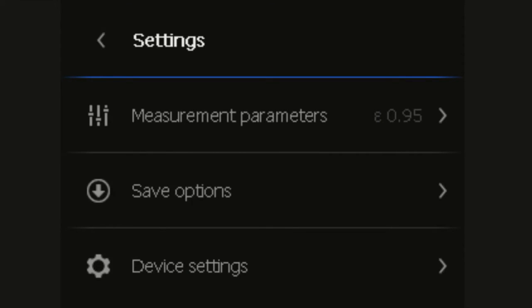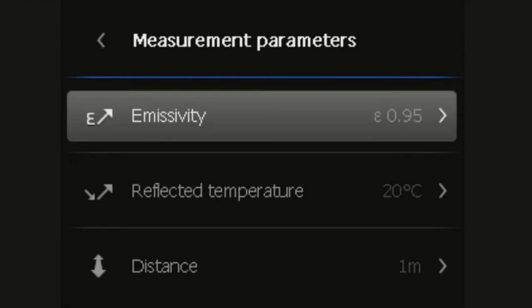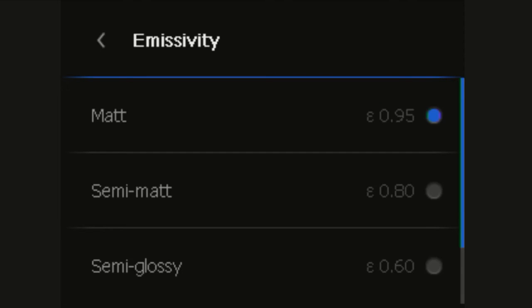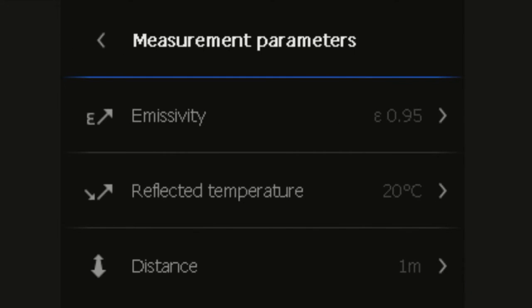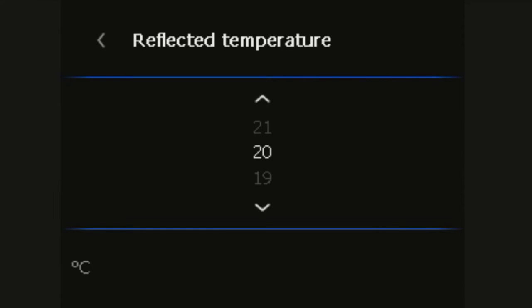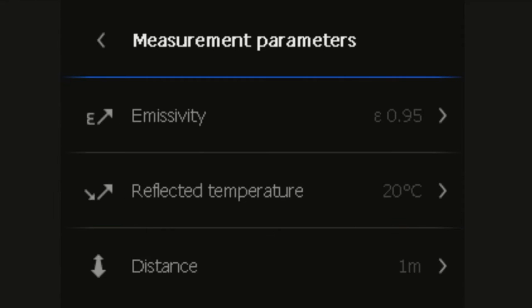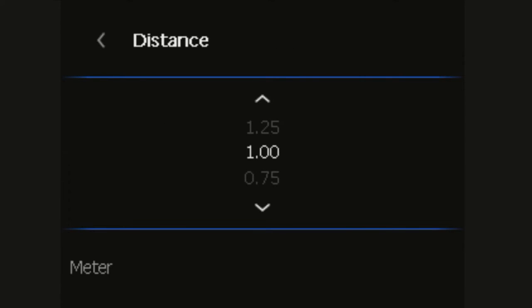Measurement parameters brings up the emissivity menu where there are three presets and a custom value to be used dependent on the surface material and the surface finish of the object you are measuring the temperature of. You can enter in the reflected temperature and set the distance to the object you are measuring the temperature of.